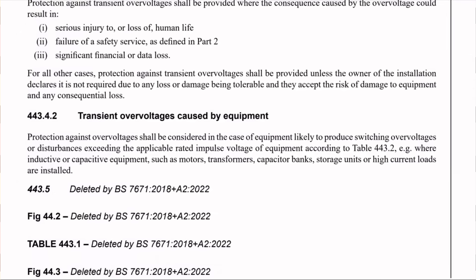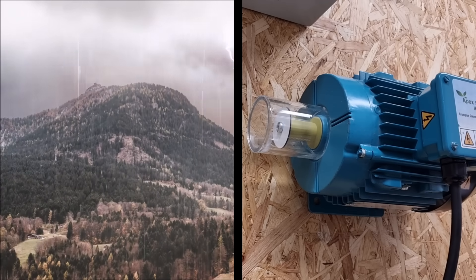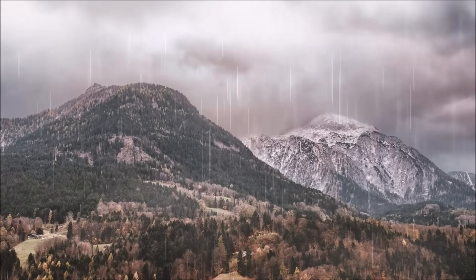However, an interesting point to note is that in regulation 443.1.1, which outlines the scope and object of this section of the regs, it has this sentence: in general, switching overvoltages have lower amplitude than transient overvoltages of atmospheric origin, and therefore the requirements regarding protection against transient overvoltages of atmospheric origin normally cover protection against switching overvoltages. So what this is saying is that surges caused by lightning strikes on the supply system are usually more severe than surges caused by machinery switching on and off. So logically, if you've protected your installation against lightning-caused surges - which is most likely happening as standard - then chances are you're automatically protected against surges caused by equipment as well.